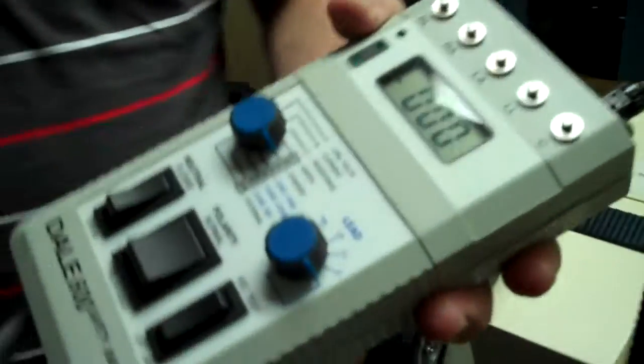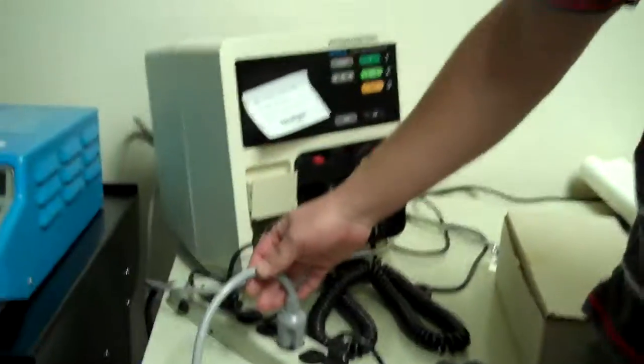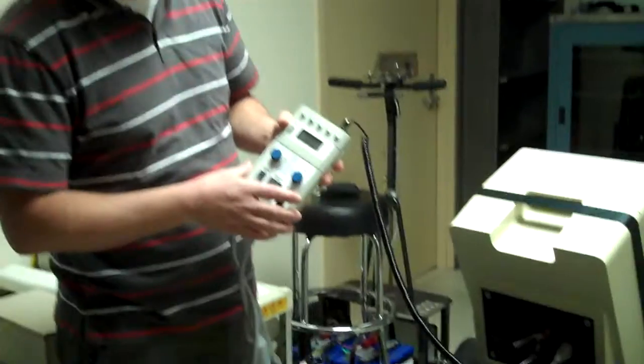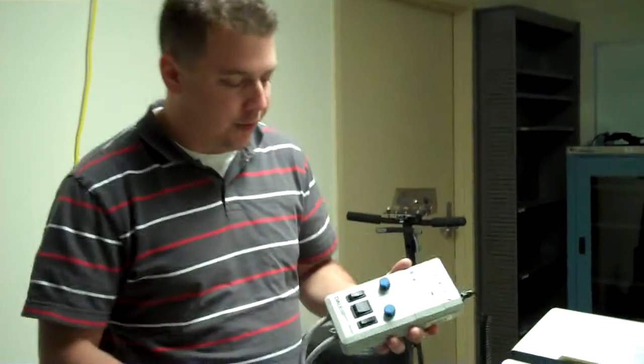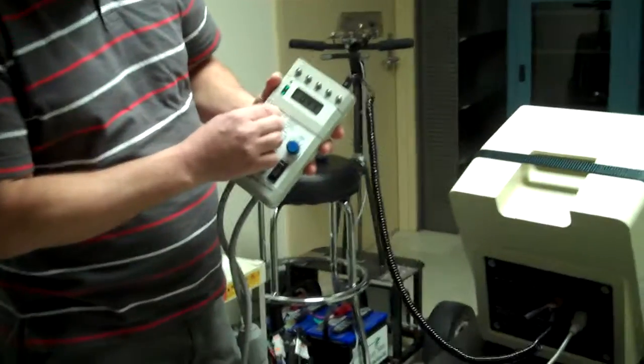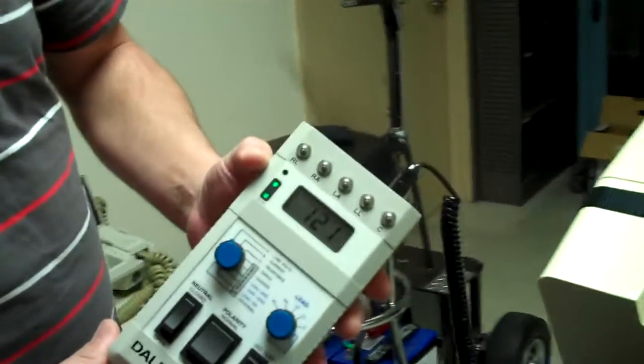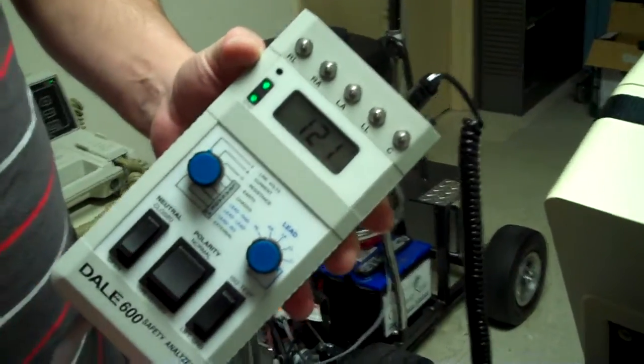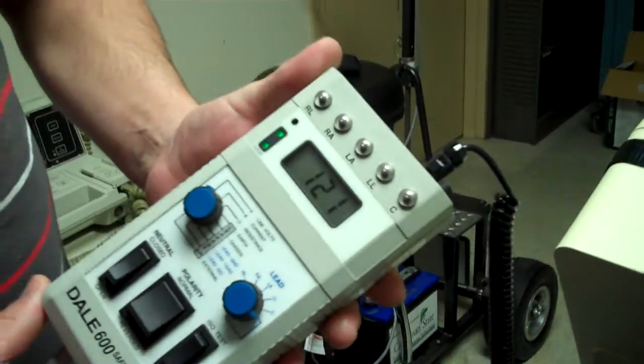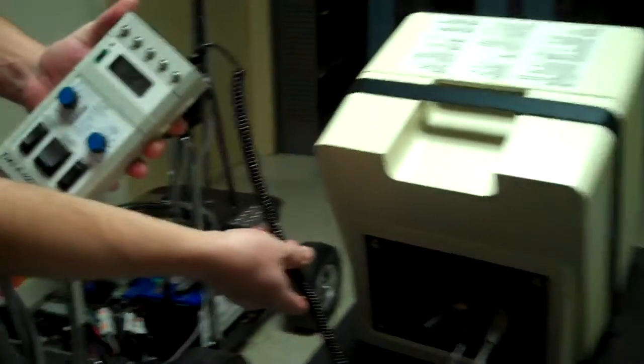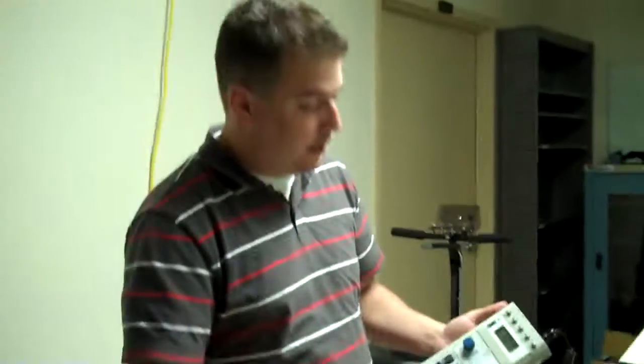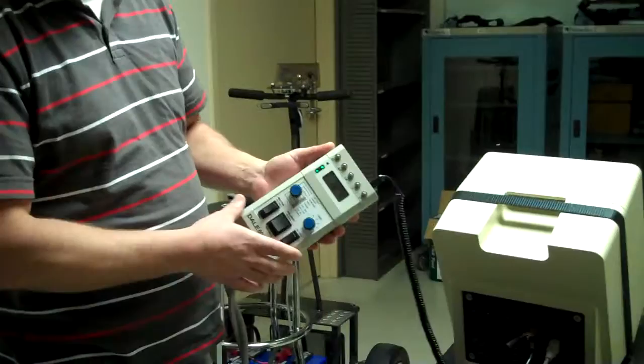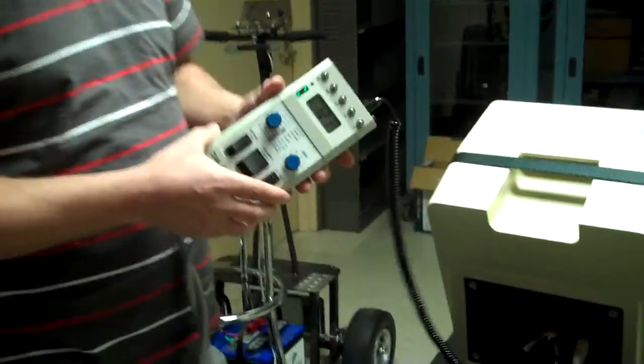So here I have the Dale 600 safety analyzer. It's plugged into our power here, and then our defibrillator is plugged into here, that way you can get a good reading on everything that's going on as far as through the electrical cord. So what we'll start with is we're going to put it up here to our line volts and just check our voltage here to make sure that that's correct, and it's reading 120 volts, which is great, right where it should be. And then we've got this cord here which applies a ground to our chassis on our defibrillator, and that's going to help us verify leakage current that is leaking into our ground from our component here, which is not good for the hospital.